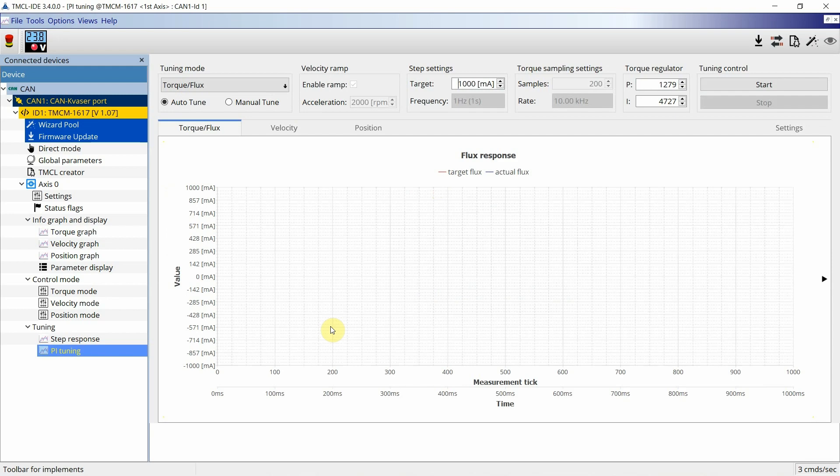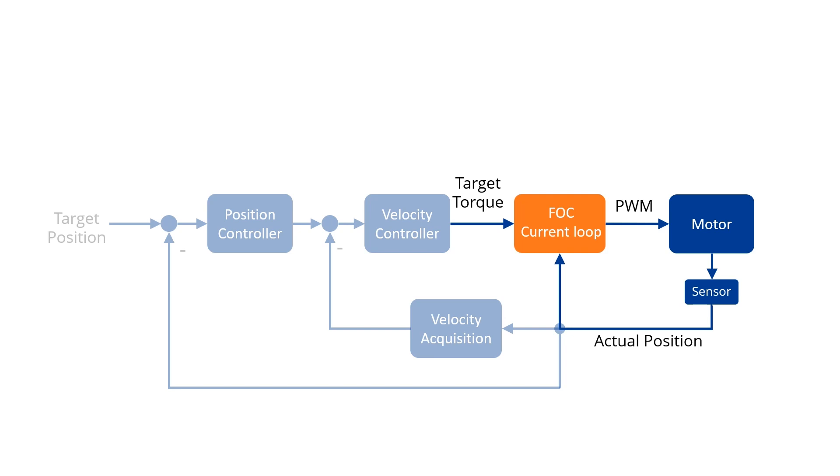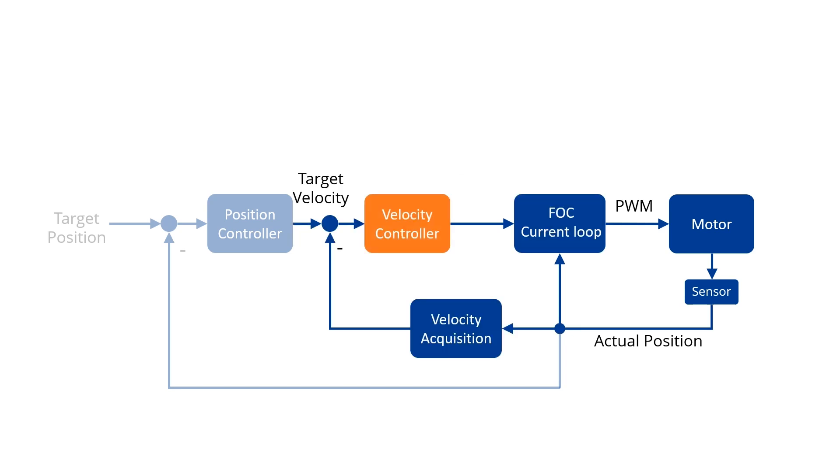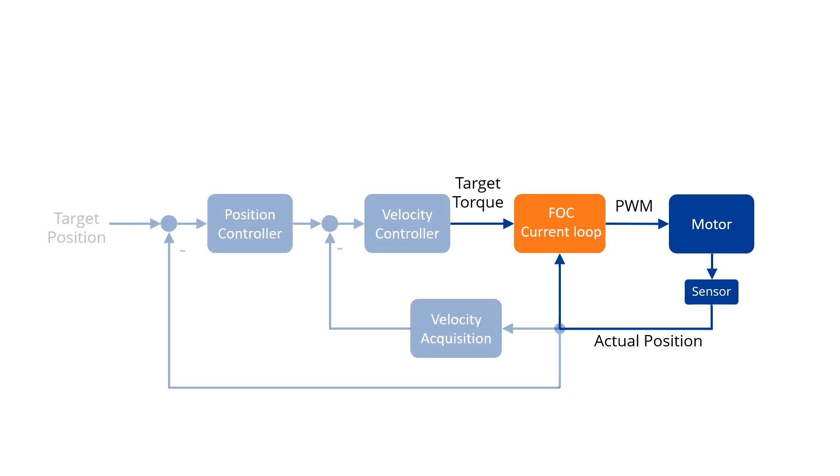During the PI tuning, three loops will be tuned. First, the FOC torque loop, secondly, the velocity loop, and third, the position loop. These three loops are cascaded and thus, as first step, the current loop as the most inner loop is tuned.